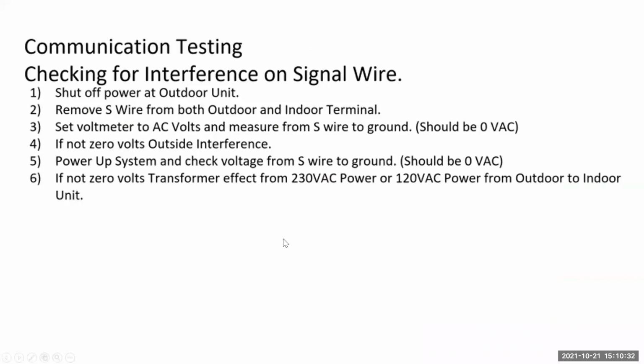For communication testing, this is what's called the transformer effect. Shut the power down. Remove your S wire from the indoor and the outdoor unit or units. Set your voltmeter to AC, and test your S wire to ground. Obviously, with no power, you should get 0. If you don't, then something's touching that shouldn't be touching.